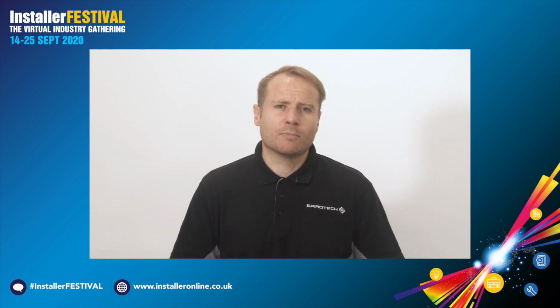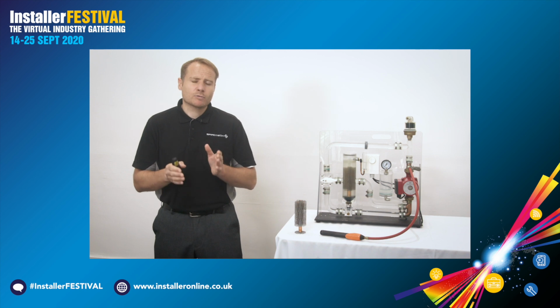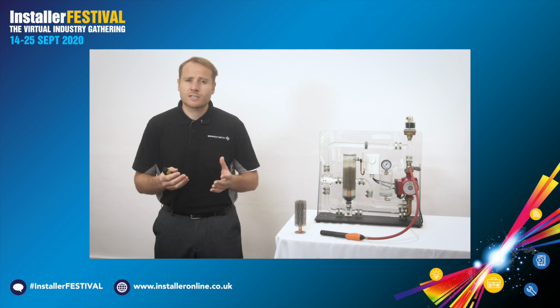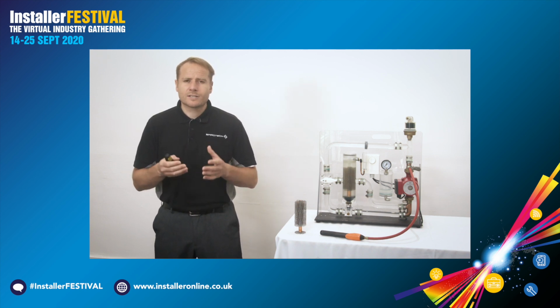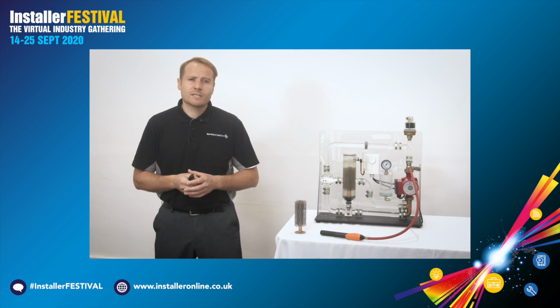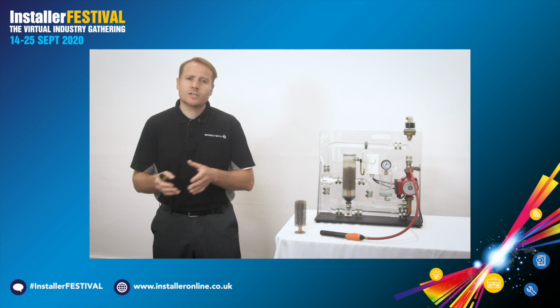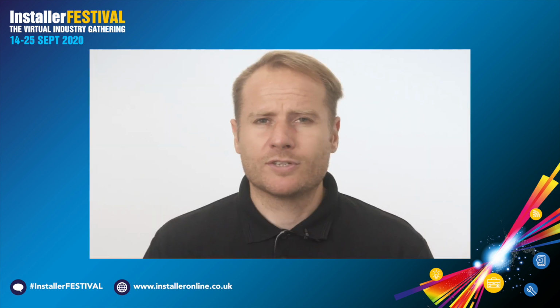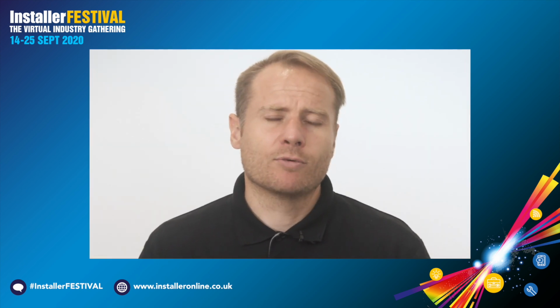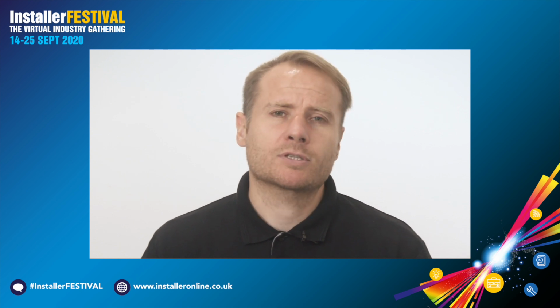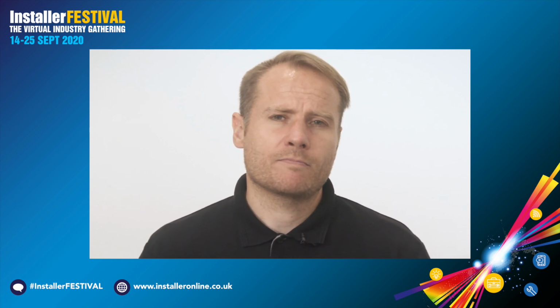As the heat exchanger in the boiler starts to heat the system water, tiny microbubbles will start to accumulate on the walls of these heat exchangers. It's the system flow flowing through the heat exchanger that carries these microbubbles from the heat exchanger into the system. The deaerator is designed to remove the liberated microbubbles from system flow.